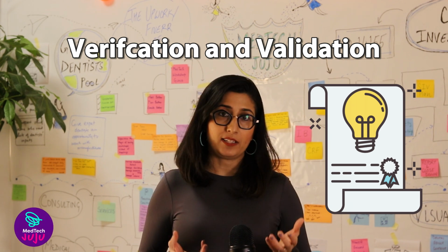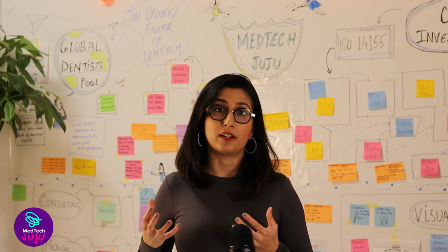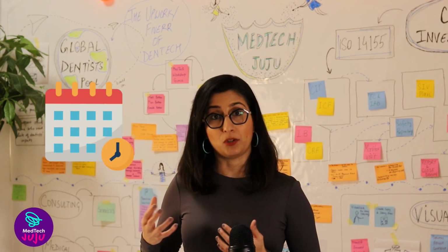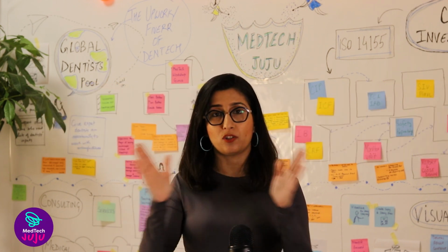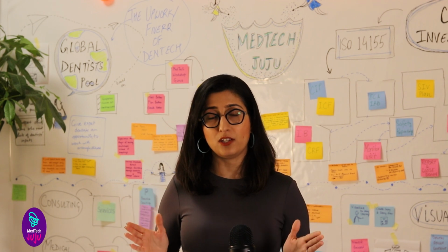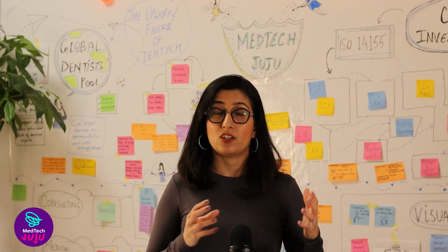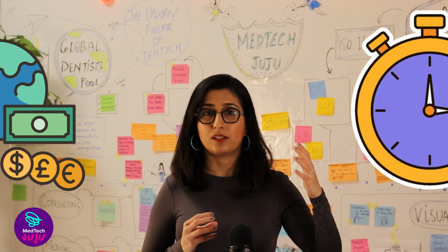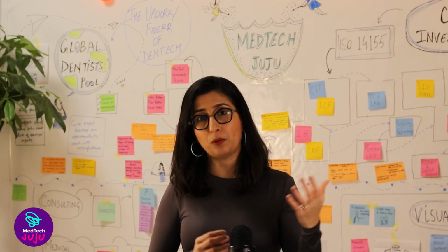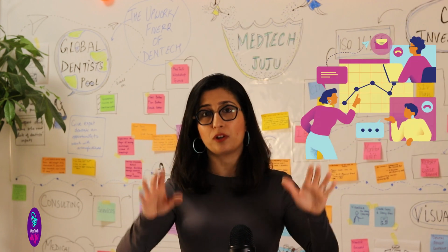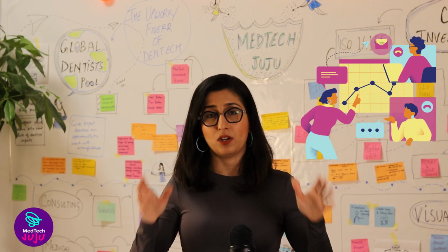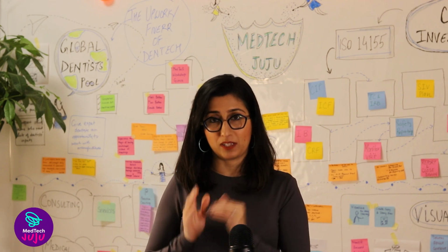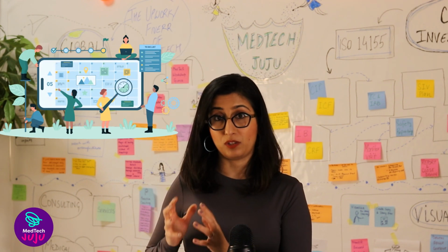The verification and validation stage is an intense part of a device's development process, and it's also time consuming because there's a whole bunch of things that need to be done during this stage. It is a little heavy in terms of time and money, because now you are testing your prototype in the labs, sending it to third-party independent vendors who are taking your device and testing every aspect of it, following very specific standards for your chosen device.